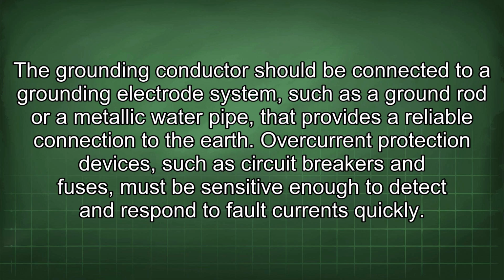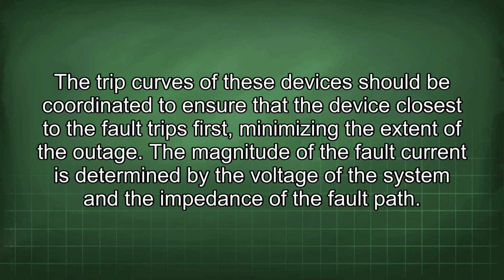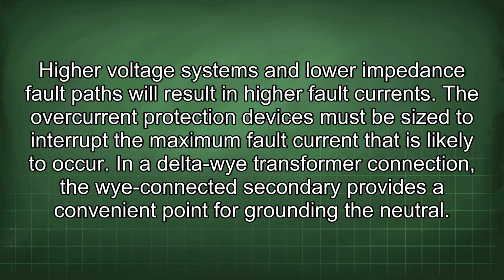Overcurrent protection devices, such as circuit breakers and fuses, must be sensitive enough to detect and respond to fault currents quickly. The trip curves of these devices should be coordinated to ensure that the device closest to the fault trips first, minimizing the extent of the outage. The magnitude of the fault current is determined by the voltage of the system and the impedance of the fault path. High voltage systems and lower impedance fault paths will result in higher fault currents. The overcurrent protection devices must be sized to interrupt the maximum fault current that is likely to occur.